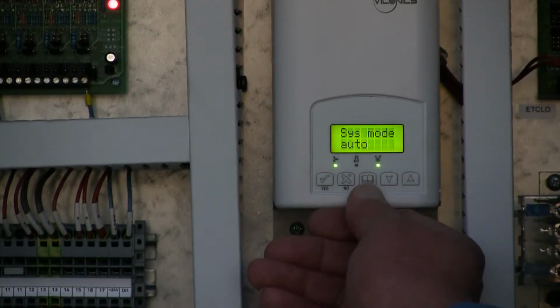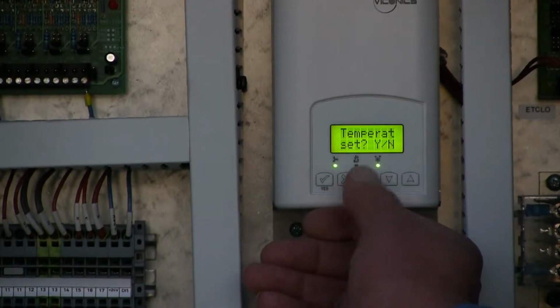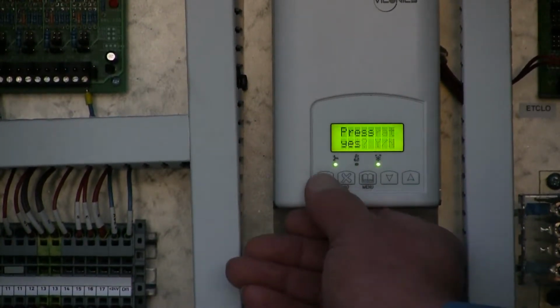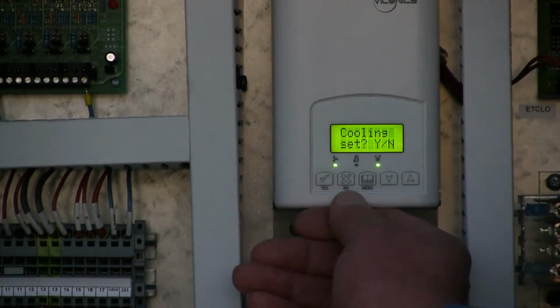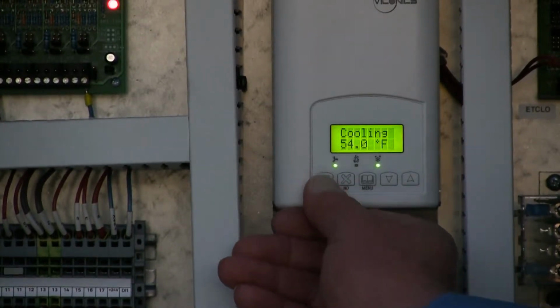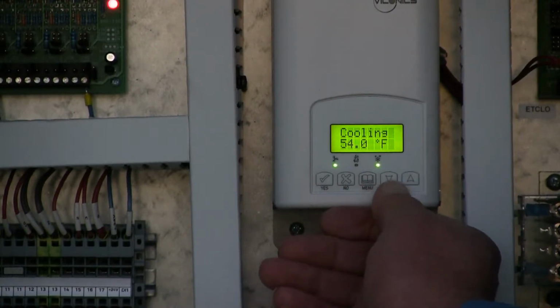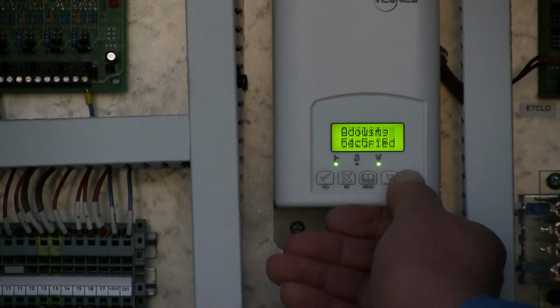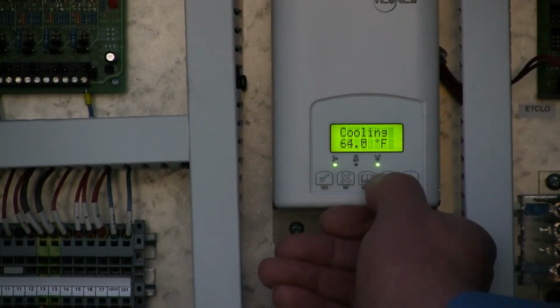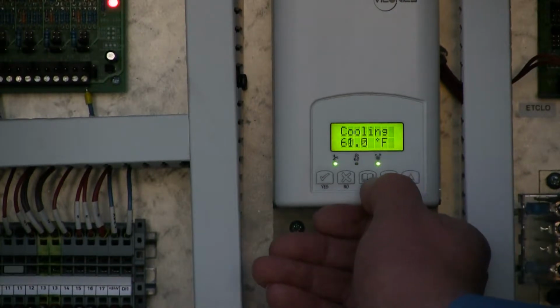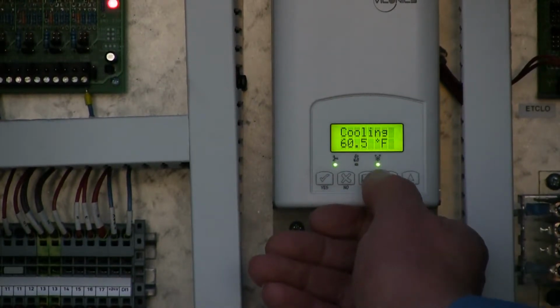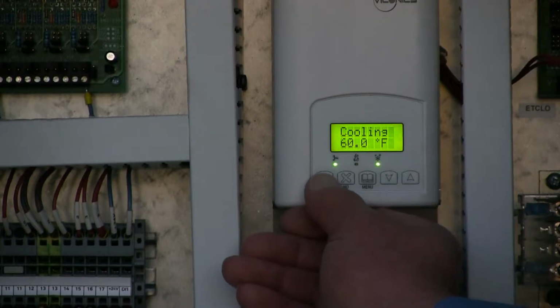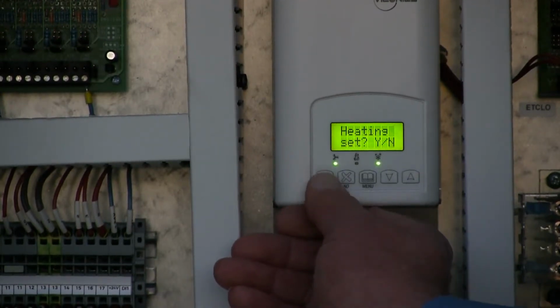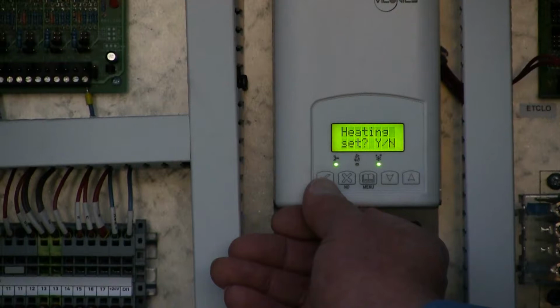So now that we've got our mode set, now we've got to set our temperature. So we're going to push the menu button again. Temperature set point, yes or no. We're going to simply say yes. Cooling set point, yes, we want to set the cooling. And then at this point it's set at 54 degrees. We're going to raise that up by just holding the arrow down for rapid, or we can pull it down slowly by tapping it. We're going to set the cooling at 60 degrees as just a demonstration. And once we've got it there, we're going to check yes by allowing, and that'll lock in the set point.